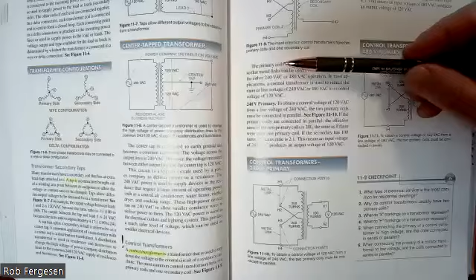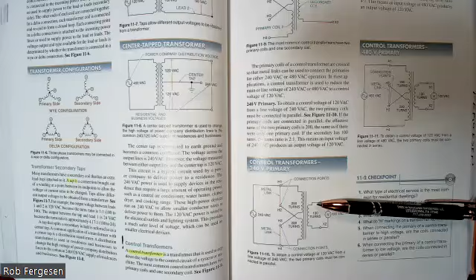And they give you a few different examples of how you hook up a control transformer. And when you buy these transformers, they will give you a diagram to hook up. They'll say, all right, if you have 480 volt, then you hook up your 480 and you'll tie H4 to H2, and that'll be 480, and H3 to H1, and that'll be another 480 line, and so forth. So it'll give you different methods of hooking up those primary coils to allow either 480, 240, or whatever the input voltage is.